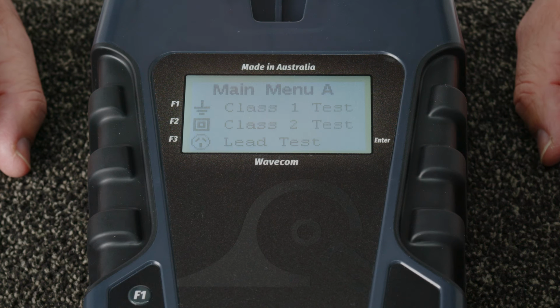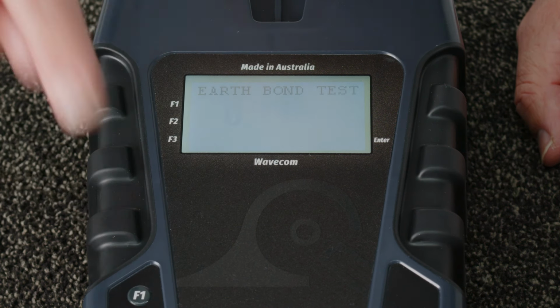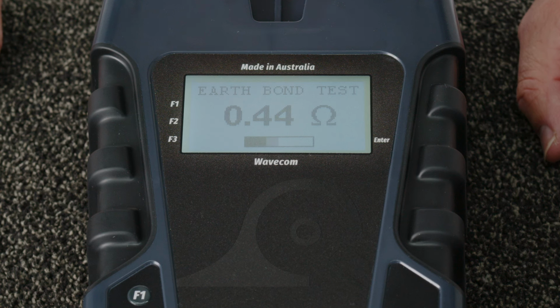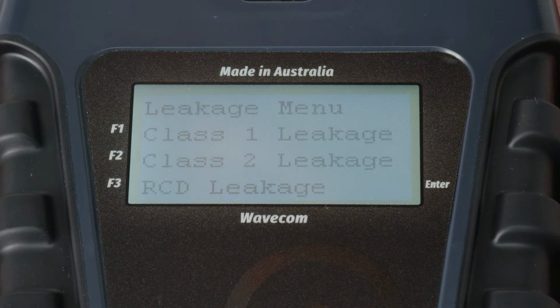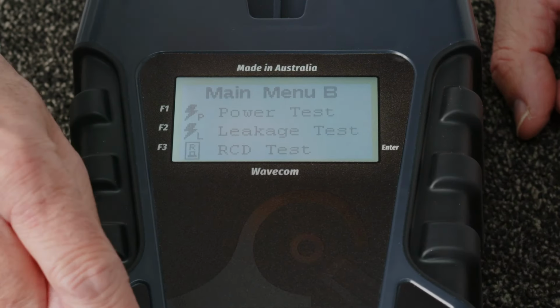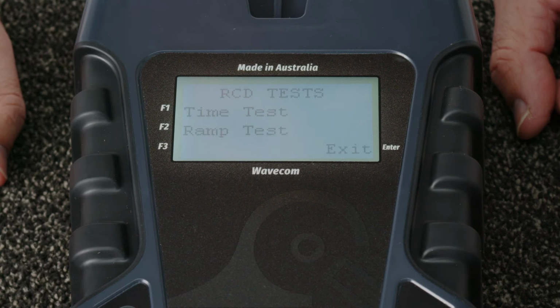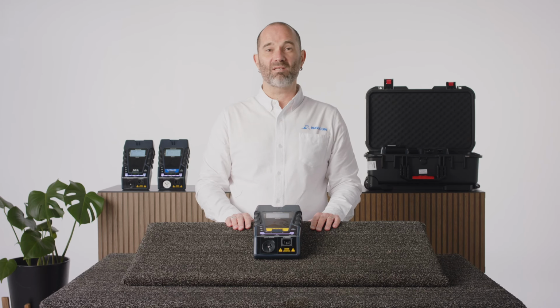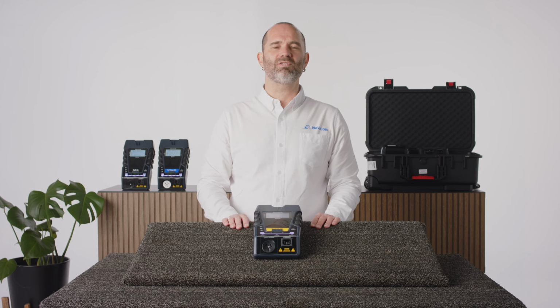These include Class 1, which is an earth bond and insulation at 250 or 500 volts. Class 2, insulation at 250 or 500 volts. Extension leads and power boards, earth bond, insulation, polarity and continuity. Earth leakage tests, and trip time and ramp current tests for testing both portable and fixed RCDs.